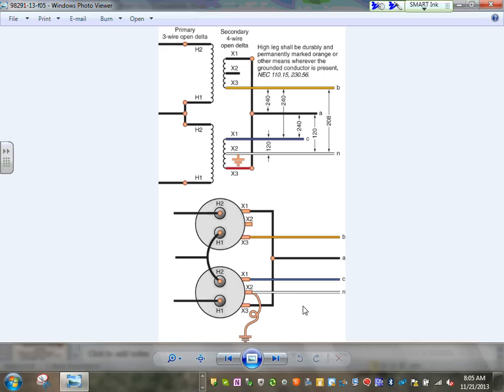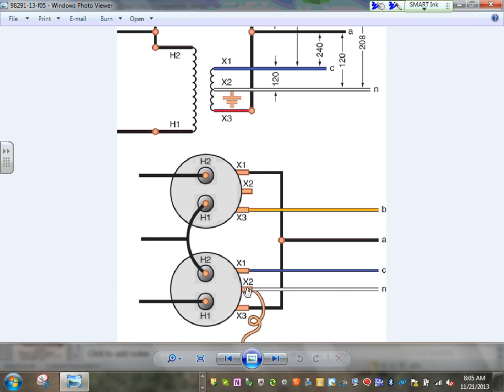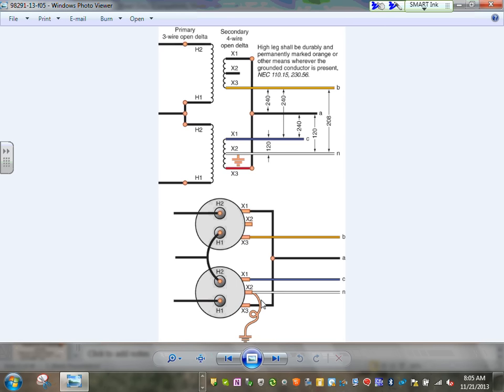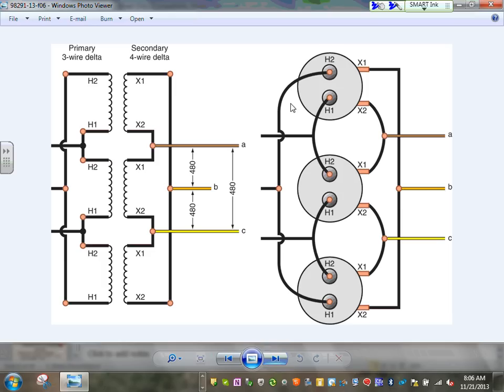Straightforward. When you make a delta, you put the coils in series and you bring a phase between every two coils. Then you take the center of one transformer, X2 here, and you ground it. So these are different connections. If you have a delta-delta, look at the delta-delta, guys.